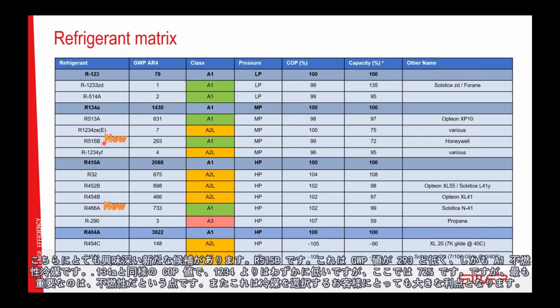There is a very interesting new candidate here, R515B. It has a low GWP of 293, and it's an A1 non-flammable refrigerant. Similar COP as R134A, slightly lower than R1234ze, but 72% here. But the most important is that it's non-flammable, and it's a huge advantage for customers choosing a refrigerant.